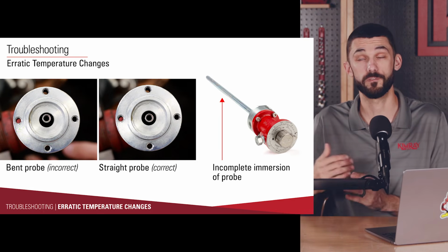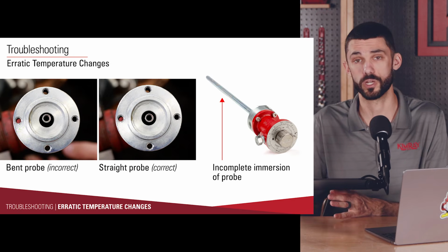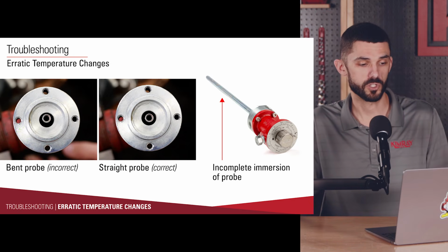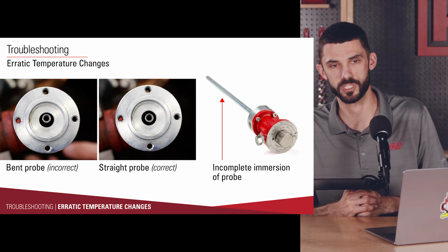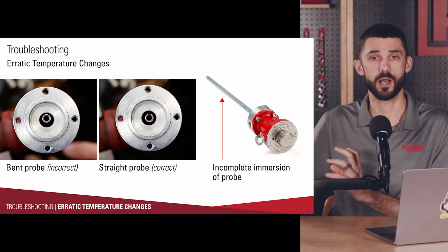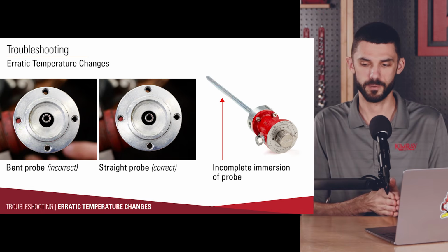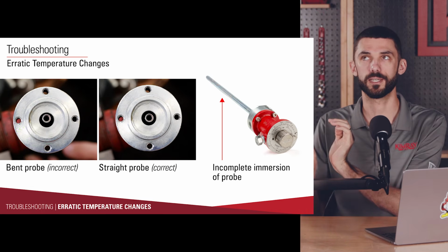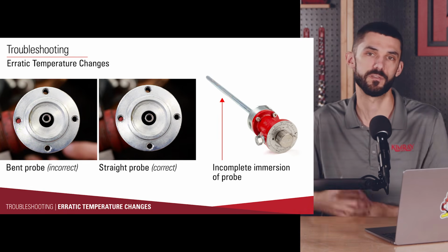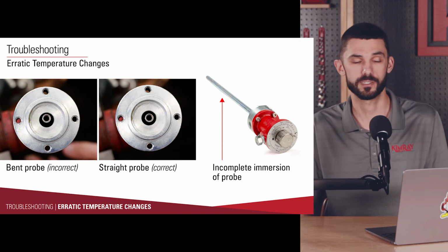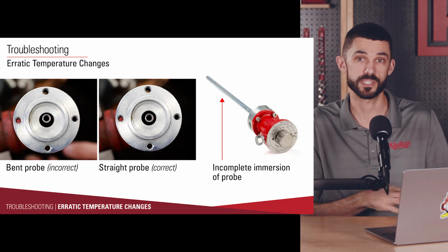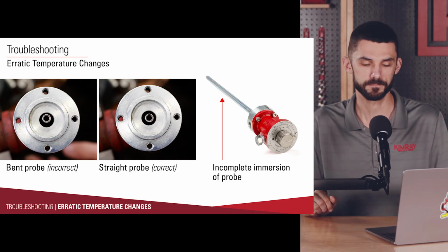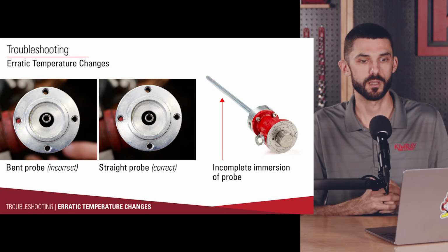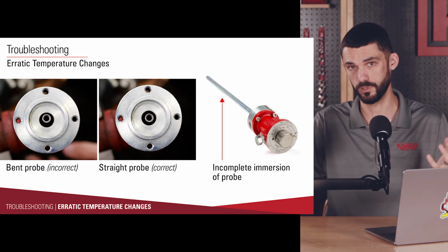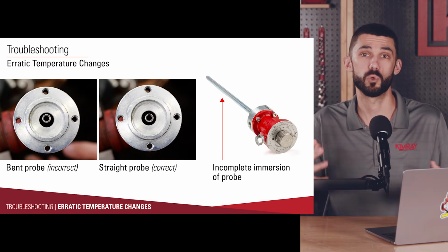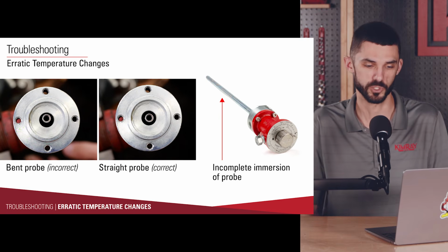Also, the probe not being fully immersed in the liquid that you're trying to control the temperature of. So you want to make sure that it's completely covered with liquid. I've had some questions about using the temperature controller in an outside bridle or in a weld neck, or where there's limited fluid around the sensing element of the T12. Ideal best practice, the temperature sensing element is inside of the vessel, surrounded by a large volume of that liquid. That's not always the case, but the more volume of fluid or liquid that you can have around that temperature sensing element, the more accurate the T12 is going to be with controlling that temperature.